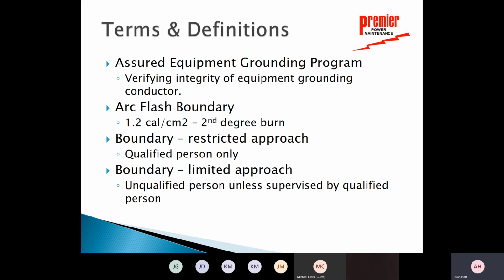Understanding our arc flash boundary, these are just definitions. That 1.2 calorie, that's a second degree burn. That is where the arc flash boundary is. Understand that at 480 volts, they don't begin the calculation for 18 inches. So the first 18 inches of your arm is not covered by that calculation. Above 480 volts, they don't begin the calculations until 36 inches. So if you're working on a 5 kV system, your whole body could be inside what that calorie calculation is.